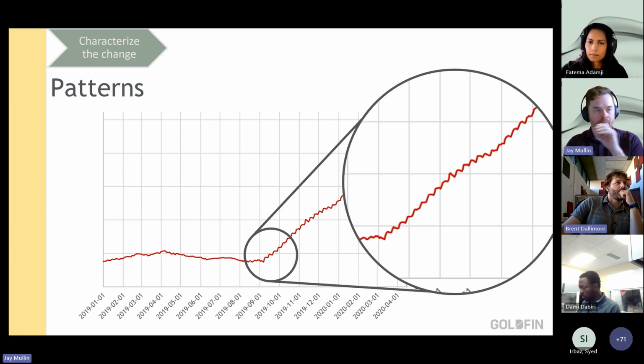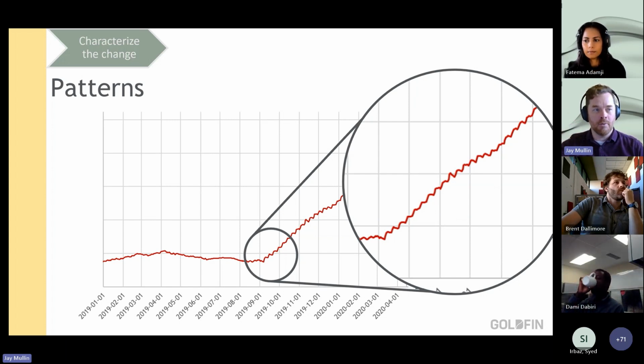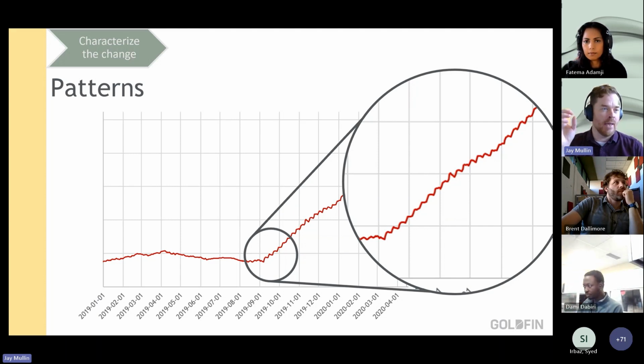Just yes or no. So during the baseline period, it does pretty well, you can see the CUSUM is pretty flat, pretty smooth, so we're doing a pretty good job of predicting what that daily energy consumption is if we just have those inputs. So we know for every cooling degree day increase, on hotter days, it's increasing our energy consumption by X amount. And a weekend is going to consume X less energy than a weekday. So it's doing a good job of predicting daily energy consumption during that baseline period where we're establishing the baseline.